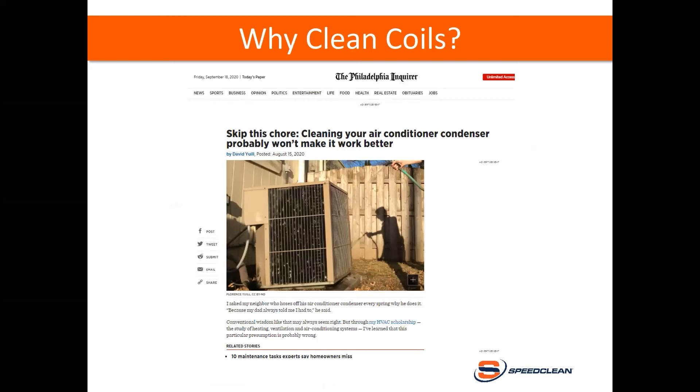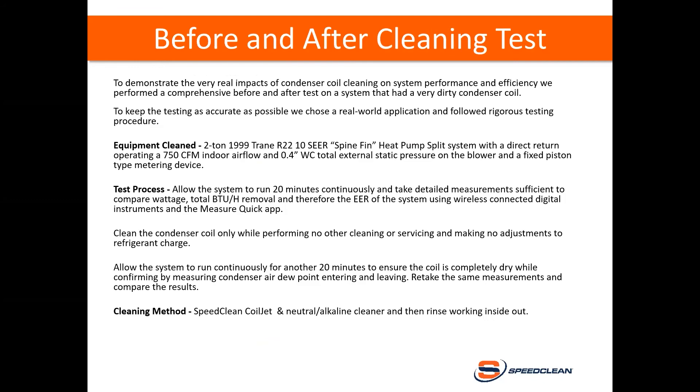Last year a professor at the University of Nebraska conducted a study — believed to be sponsored by ASHRAE — which appeared to indicate that cleaning condenser coils made no difference on system performance and efficiency. To summarize the results: washing the air-side fouling of condensers does not have a significant effect on heat transfer capacity, even though it significantly decreases the coil's air-side pressure drop. In some cases fouling can even increase heat transfer capacity, and washing with detergent had no meaningful advantage compared to washing with water only. This got our friends at the HVAC School thinking — could this data be correct? Anybody who comes across a condenser cutting out on high head pressure with dirty fins will tell you the coils need to be cleaned, and nine times out of ten that solves the problem.